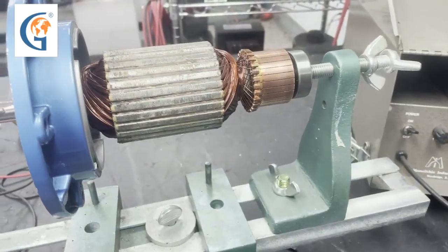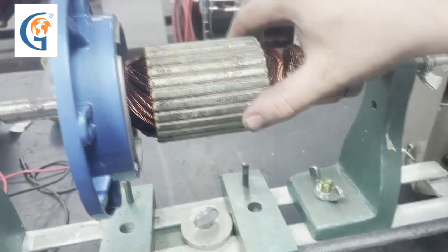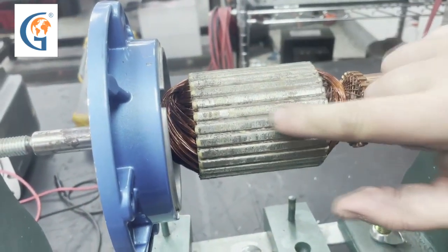Those tests look like a good normal armature. We see that we have quite a bit of contaminant on this rotor.